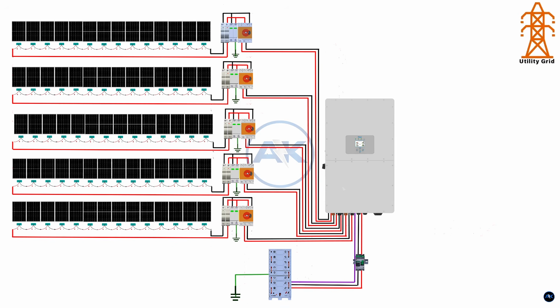Step 6. AC side connections, grid and loads. Now we move to the AC side connections, starting from the grid and ending at the building loads. This system uses a three-phase supply, which includes L1, L2, L3, neutral, and ground. Before making any connections, ensure the grid supply is completely switched off and locked out for safety.